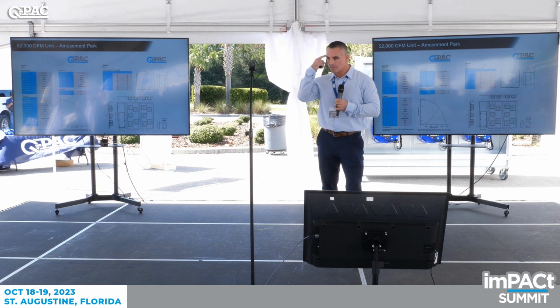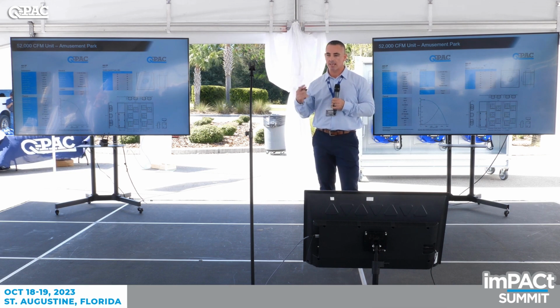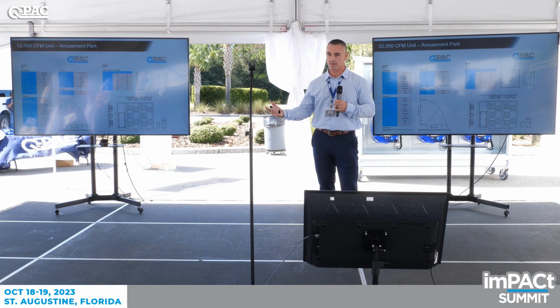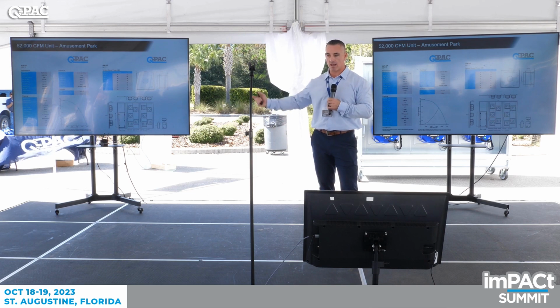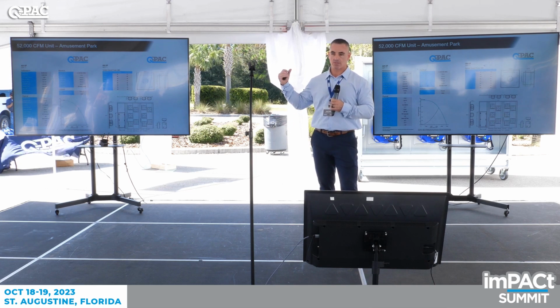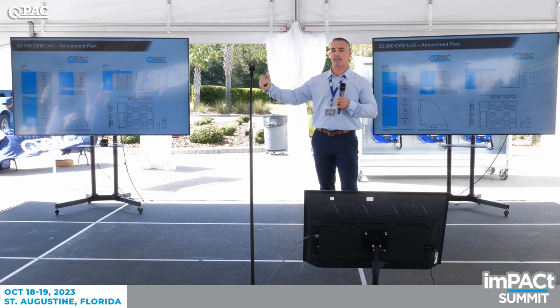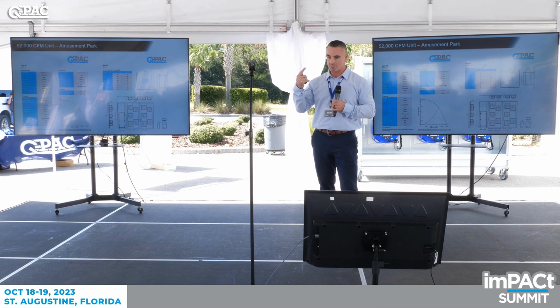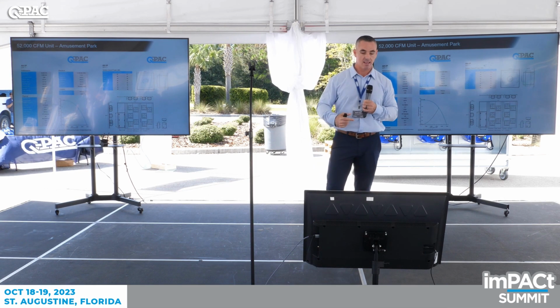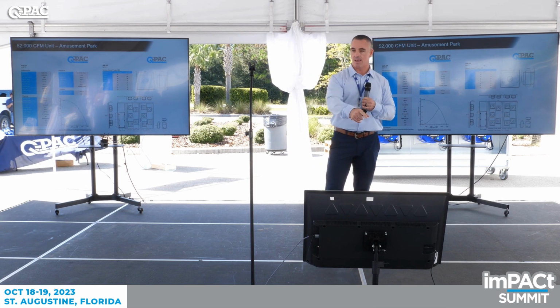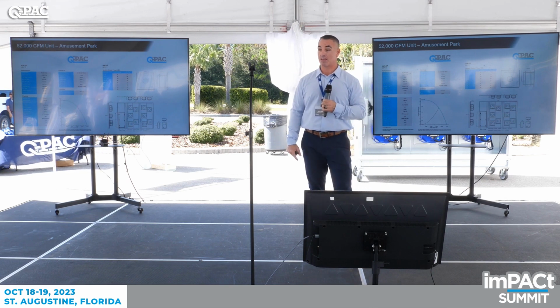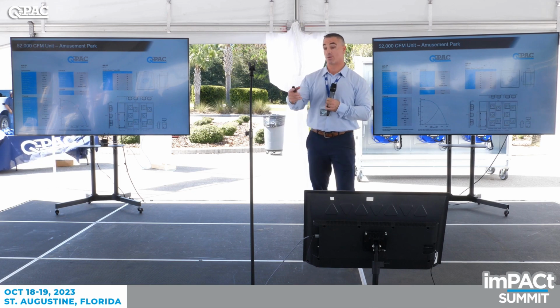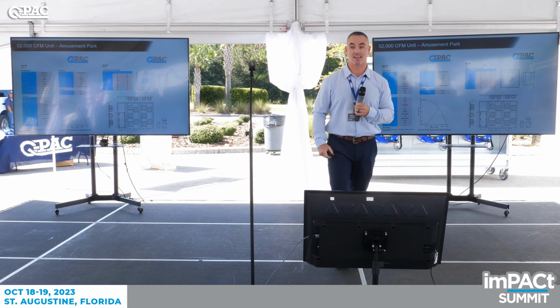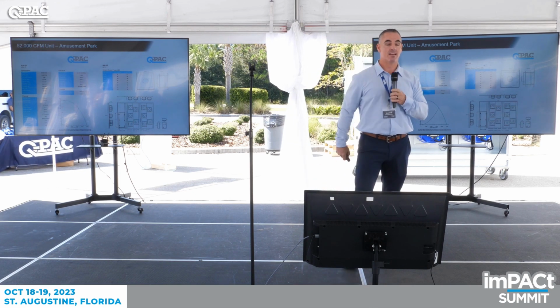And then you gotta use your engineering brain a little bit and think about what type of system we're dealing with. How long's the run? Maybe they have some data on what their external static pressure is going to be. They run at 1.5 inches. You go through all those checks and balances internally in your head, and then you get your selection. And then I try to max out that fan and see what kind of room I have. If I need to go to a different fan, I go to a different fan. Yeah, it's great.